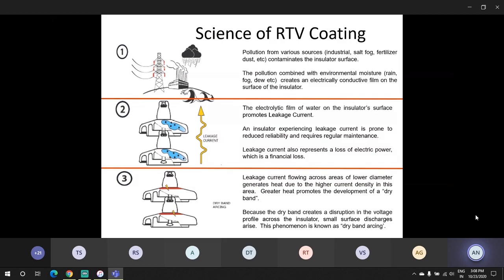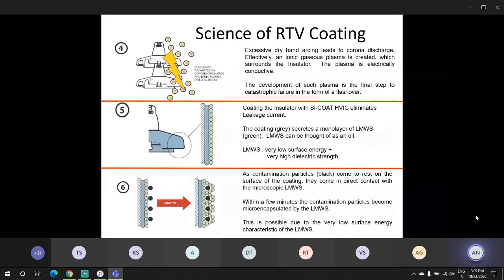This electrolytic film on the insulator promotes the leakage current and later develops into dry band arcing, which necessitates cleaning or hot or cold line washing on a regular basis to prevent this phenomenon. And if it is not attended to, it leads to a flashover and interruption, or failure, of the insulators. So what we propose is to apply a very thin coating, approximately 400 to 500 microns, on the insulator.